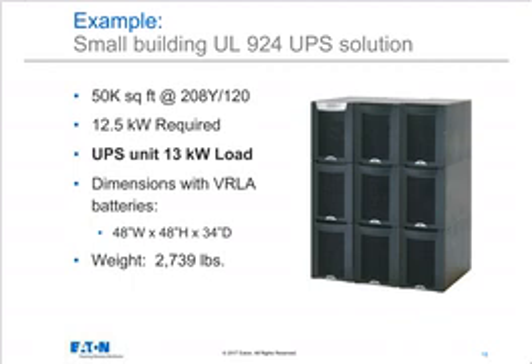And if you look at the picture, it looks like 9 identical black blocks. One of them is the UPS electronics, rectifier, inverter, and battery converter. The other 8 of them are crammed with batteries. So it's relatively compact for 90 minutes of backup, but we're still talking about a very heavy device. Hopefully we'll be able to talk to our clients soon about lithium-based batteries that will save probably 40 to 60% in both the weight and the size, but not quite available yet.